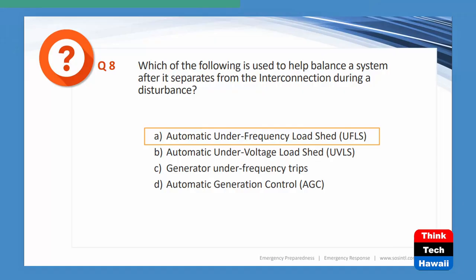You got A, automatic under frequency load shed, UFLS. You got B, automatic under voltage load shed, right? You have C, generation under frequency trips, and then D, automatic generation controls, AGC. So what do we want to accomplish here with this particular problem, right? So you want to balance a system after it separates from the interconnection, right?